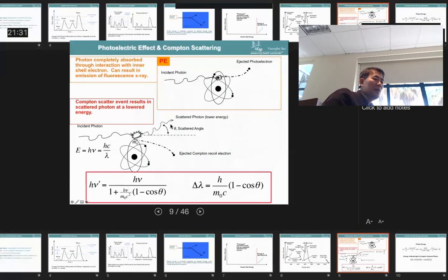So scatter is the common culprit for having lost some energy and then some kind of dirty component of the energy spectrum, because a scattered photon like this could even escape completely out of the detector system. Also, if a scattered photon is detected, it's another photon recorded by the radiation detector. But the scattered photon is not the same energy as the incident photon, meaning that the energy of the scattered photon detected by the radiation detector will be lower than the peak energy of the incident photon.